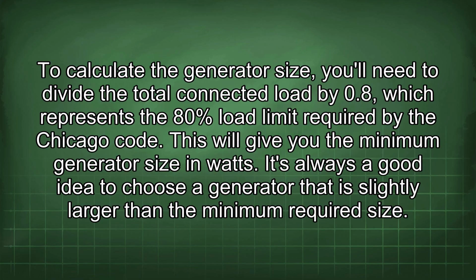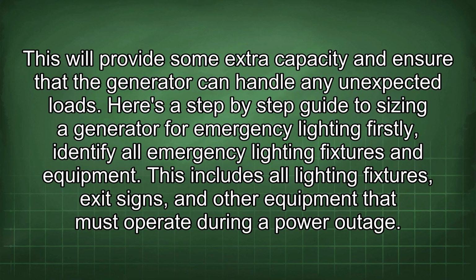It's always a good idea to choose a generator that is slightly larger than the minimum required size. This will provide some extra capacity and ensure that the generator can handle any unexpected loads. Here's a step-by-step guide to sizing a generator for emergency lighting. Firstly, identify all emergency lighting fixtures and equipment. This includes all lighting fixtures, exit signs, and other equipment that must operate during a power outage.